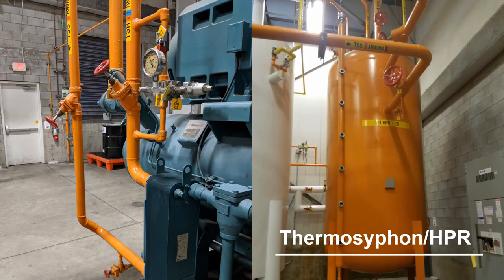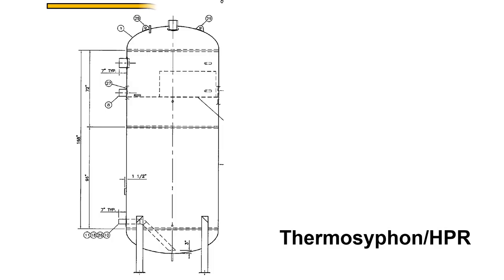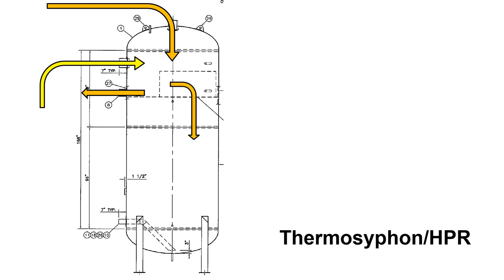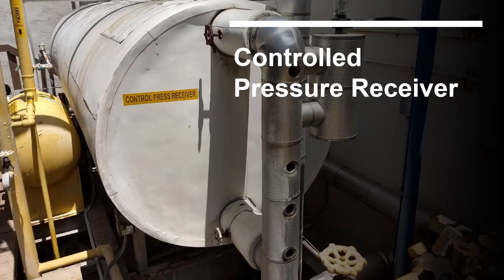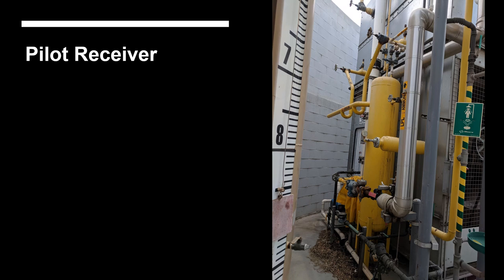A variation of a standard high pressure receiver is the combination thermosiphon high pressure receiver. In this arrangement, the vessel has an internal chamber located near the top of the vessel. Liquid from the condensers flows into the top of the vessel and collects inside the thermosiphon chamber so that it can be supplied to the oil coolers. Overflow from the thermosiphon chamber collects at the bottom of the vessel, which serves as a standard HPR. Another variation is the controlled pressure receiver, which operates at an intermediate pressure between the compressor discharge pressure and the suction pressure. Smaller systems may be configured with a pilot receiver; since pilot receivers are physically small, they generally cannot hold the system charge, and the level is maintained through the use of a float valve.